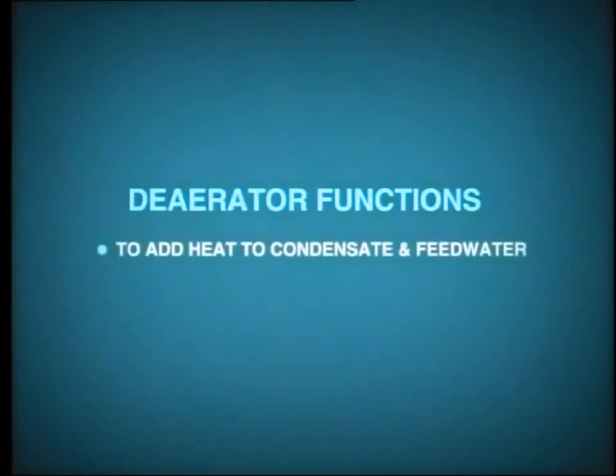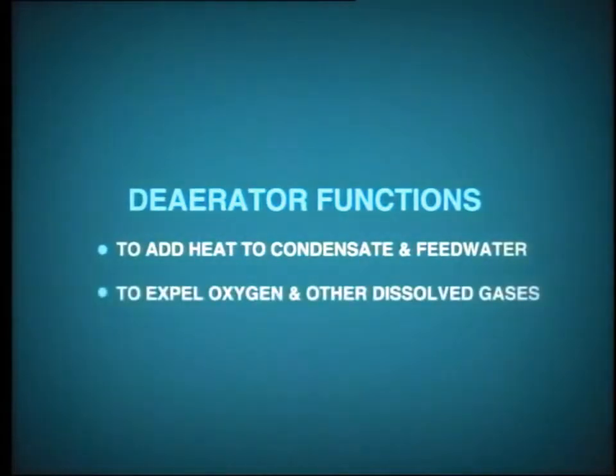This is the deaerator. The deaerator actually has two functions: to add heat to the condensate and feed water to improve cycle efficiency, and to expel oxygen and other dissolved gases from the boiler feed water. The presence of dissolved oxygen in feed water is a prime cause of corrosion in boiler tubes, so removal of as much dissolved oxygen as possible is essential. Normally we try to limit dissolved oxygen in feed water to as low as two or three parts per billion.